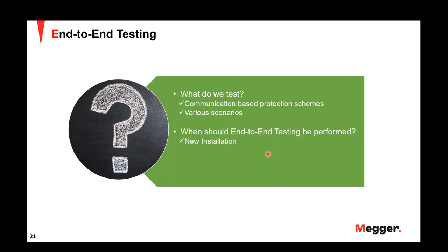So when should you perform end-to-end testing? When you have any new installation of this kind of scheme, it's always a good thing to perform end-to-end. You can do this in maintenance testing. You could also do that with the breaker involved, so the breaker operations are also verified with respect to the scheme. Like I said before, it helps a lot with troubleshooting this particular scheme, the settings, and the way the scheme is designed. If you modify or change a setting, you can perform end-to-end again to validate the scheme.